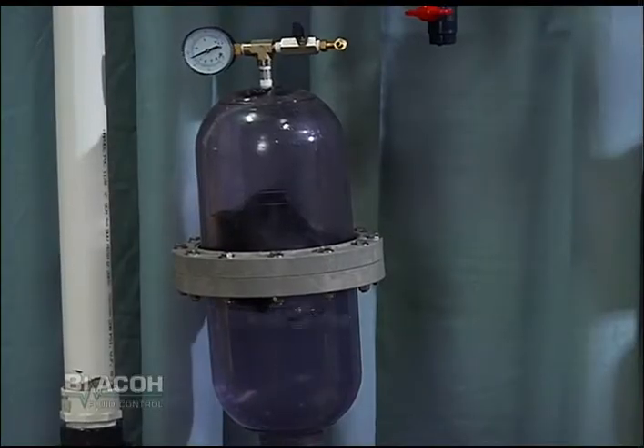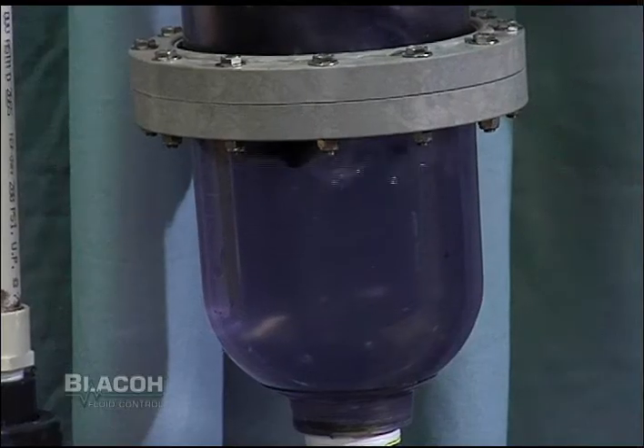As we tune in the inlet stabilizer, we can see in this transparent inlet stabilizer that the pump pulse or water hammer is now being absorbed inside the inlet stabilizer instead of slamming into the pump. What occurs is that as this acceleration head from the high tank flows down and the inlet valve balls close in the pump, they momentarily stop the flow and a pressure spike is created.